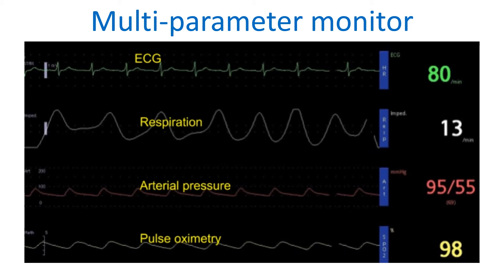Monitors can give out alarms if heart rate or any other parameter is beyond the set limits. Alarms should be taken considering the current physiological state of the person. Someone with continuous tachycardia due to illness will need a higher upper rate cut-off to avoid frequent alarms.